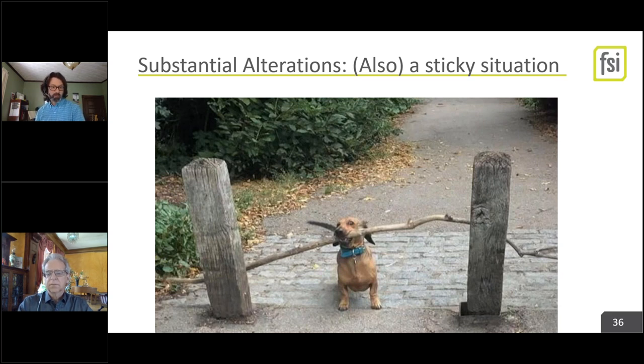But the long and short is you can do it with equipment or you can do it with a combo, but you could probably keep most of your building piping either way. And you can keep most of your terminal equipment if you're willing to jump through the hoop. And then the third example, condensing boilers that often operate at 120 degree return, 140 degree supply. That's living on the edge of what current air-to-water heat pumps or heat pump chillers, again, same thing, can do. But it is possible, and knowing engineers of the past aren't that different from engineers of the present, there's probably a healthy safety factor, and you might find that you could live at 130 degrees and live well within an air-to-water heat pump. And that would be almost a one-for-one replacement for what had been a piece of gas equipment.